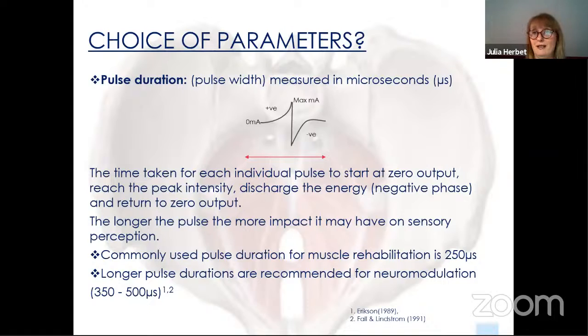The longer the time, so the higher the number of the pulse, the more impact it might have on sensory nerves. So the most commonly used pulse duration for muscle rehabilitation in the pelvic floor is about 250 microseconds, but sometimes people shorten that even lower to 125, to avoid any stimulus or too much stimulus on the sensory nerves. And there's a payoff between shortening the pulse and getting sufficient intensity that the patient can tolerate to make the muscles actually contract.